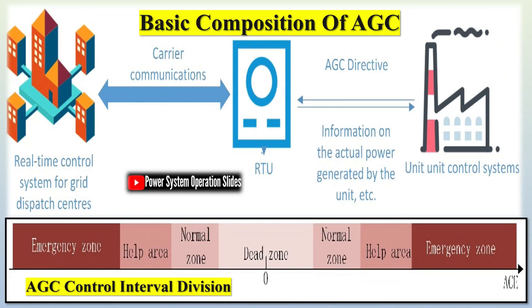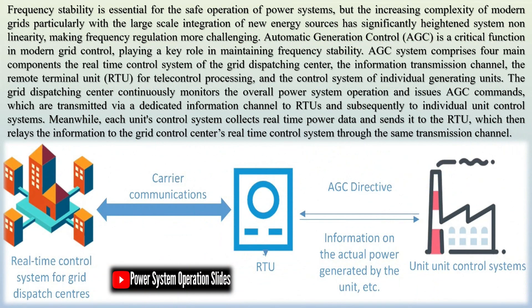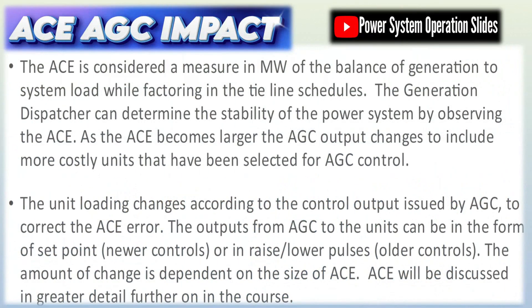AGC is a key enabler in transitioning to cleaner energy while upholding power system security and performance. AGC is a real-time control mechanism in power systems that continuously adjusts the output of multiple generators. Its main mission is to balance generation and load so that the system frequency stays near its nominal value — typically 50 or 60 Hz — and the power exchanged via tie lines with neighboring control areas remains as scheduled. AGC acts as the grid's balancing act by rapidly compensating for load fluctuations, renewable output variability, or even generator outages.